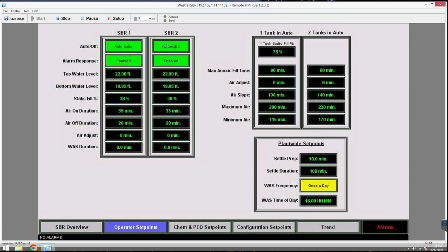So right now the bottom water level is at like 19.8, and that usually has been trending up. It really should be down at 17. It's been trending up because obviously a way to make sure the decants are clean is move that bottom water level up, right? Because then the decant arm doesn't go as deep. So we have these kind of smaller batches, more frequent, I would say. Yeah, more frequent, smaller batches, because the settleability isn't there.